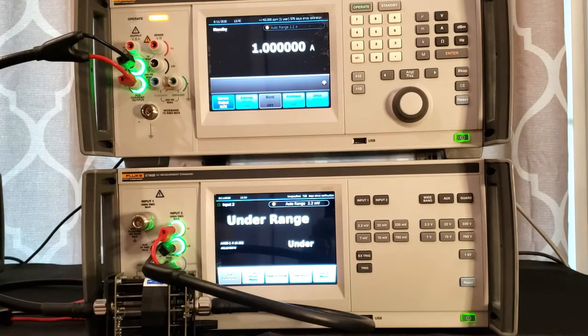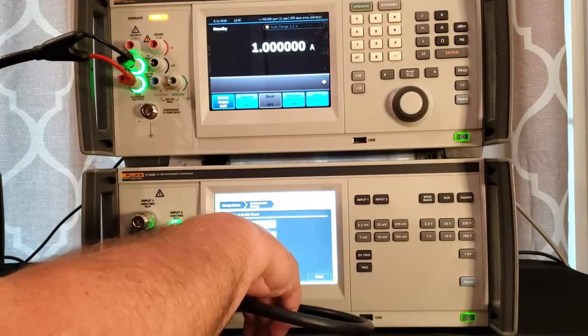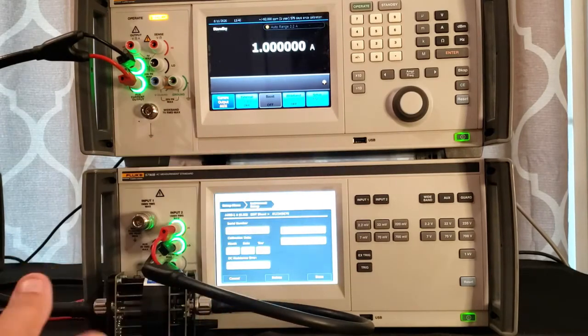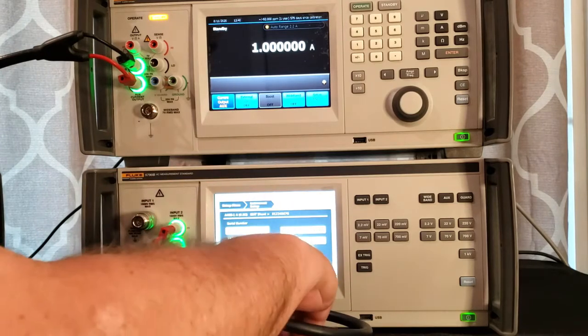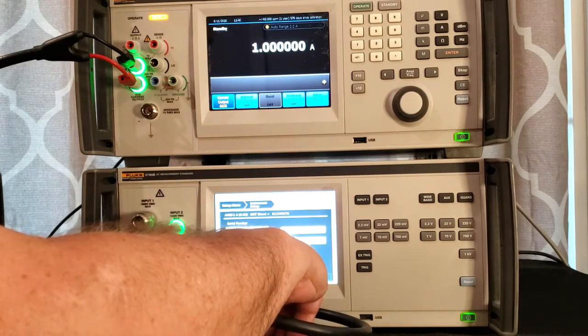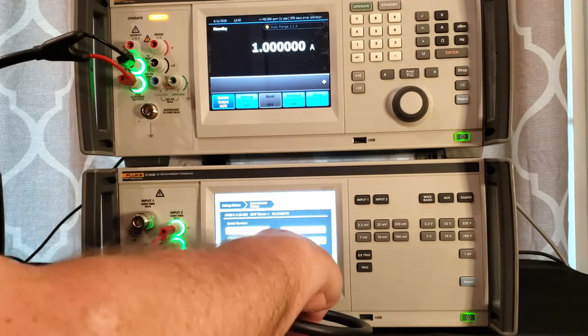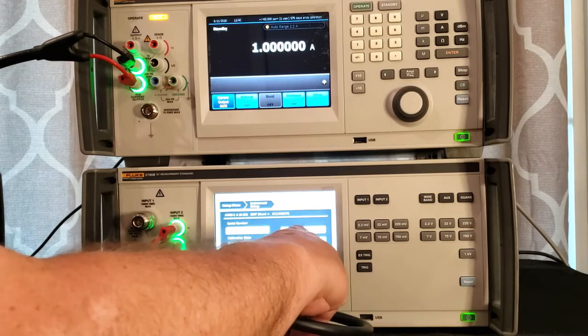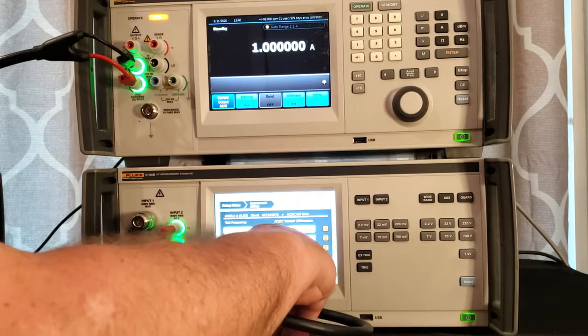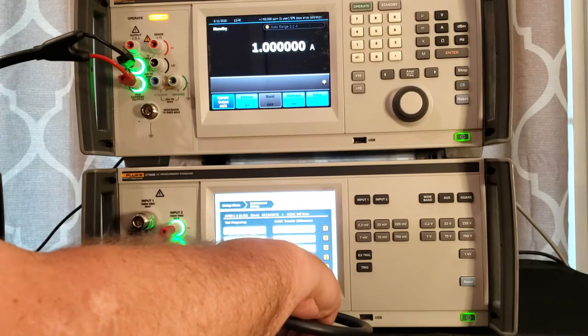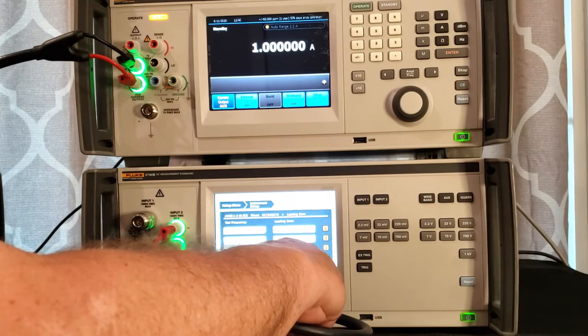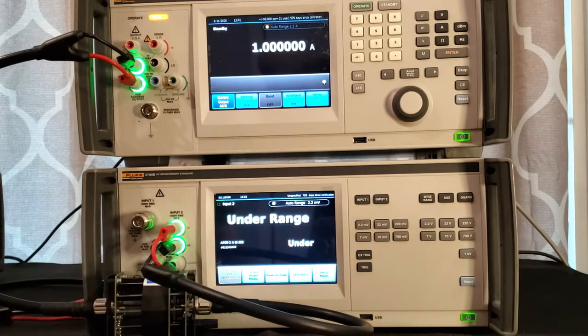The first thing we need to do is make sure that we have the calibration data set up. If you have your calibration data, you can enter in your DC resistance error off the certificate of calibration. You can enter in your AC-DC difference across the different frequencies. You can enter in your loading error. Now it's set up.